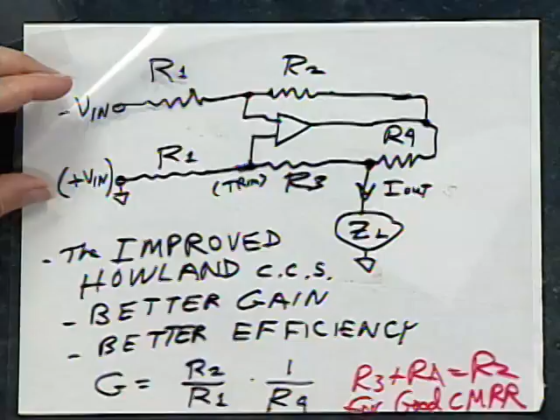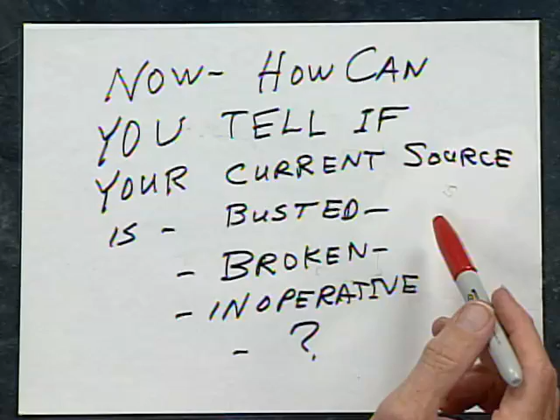That's a hard circuit to analyze. Nobody analyzes it, and I only do it once a year. You've got a current source, a 4 to 20 milliampere current source. It broke. It's not even 4 milliamperes, or 3, or 2, or 1. It's less than a milliampere. Something's busted, something's wrong. How do you detect it?